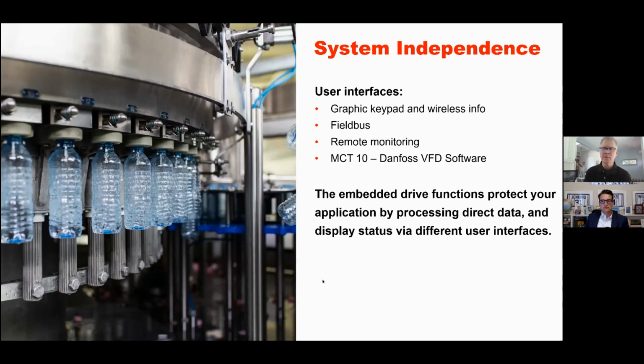So with that software, it's hot swappable. We can walk up to a drive that's running on a production line, and we can plug in with a USB cable. And we can bring up a lot of different values, which are very beneficial to the maintenance personnel and technicians. But we can also bring up the condition-based monitoring. So if we're seeing a warning or we're getting information back to say we're having warning 1, warning 2, we can actually plug into the drive and take a look at those warnings and see where we are in a level. So it's a great software to use, and it's extremely simple to use.